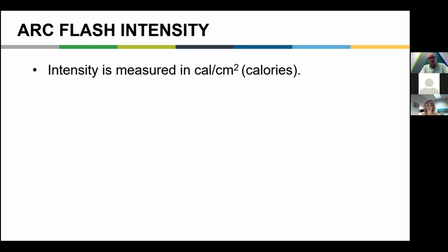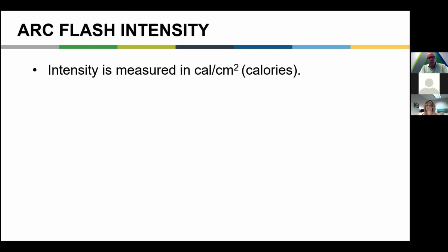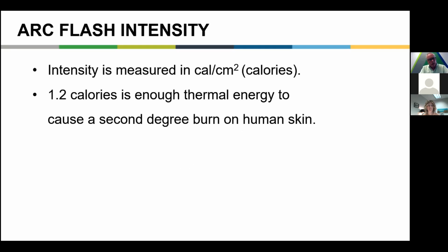Okay, so arc flash intensity. How do we measure this very, very dangerous condition? We measure it in calories per centimeter squared, simply calories when we're talking about arc flash. 1.2 calories is a very important number. It's enough energy to cause a second-degree burn on human skin. And for those of us who specialize in this area, that 1.2 is a very important threshold.